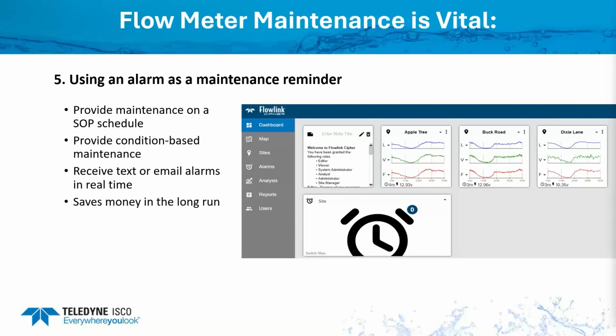And so with your software, or like in this case, the FlowLink Cipher, you could even have different gadgets on your dashboard that show your signal and spectrum strength. And when there is an alarm condition, like my ratio starts to drop to 40% or lower, you can have the software send out a text message or an email alarm to let you know when to go out and start doing maintenance on the sites.